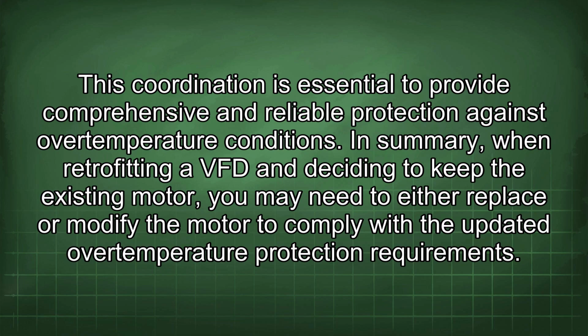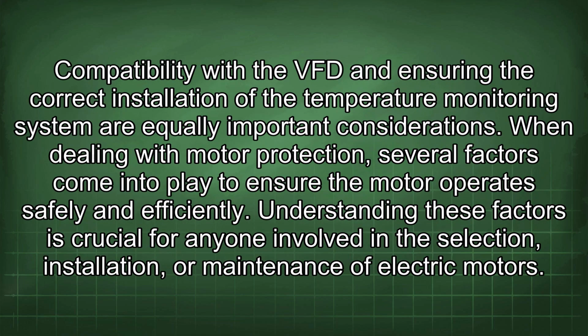In summary, when retrofitting a VFD and deciding to keep the existing motor, you may need to either replace or modify the motor to comply with the updated overtemperature protection requirements. Compatibility with the VFD and ensuring the correct installation of the temperature monitoring system are equally important considerations.